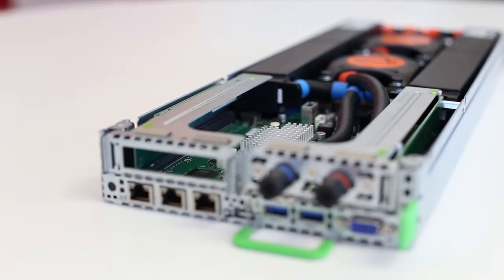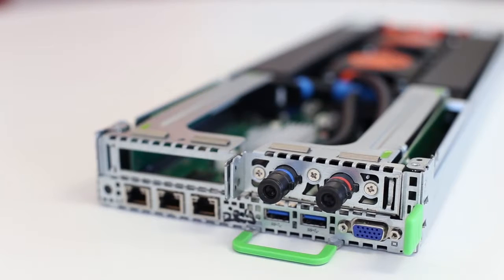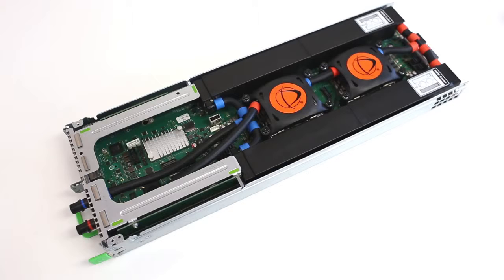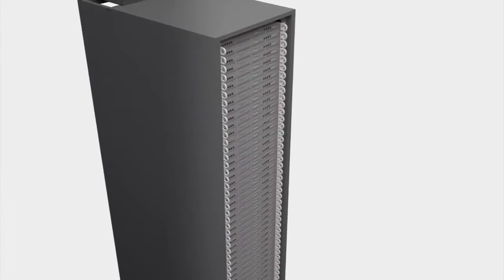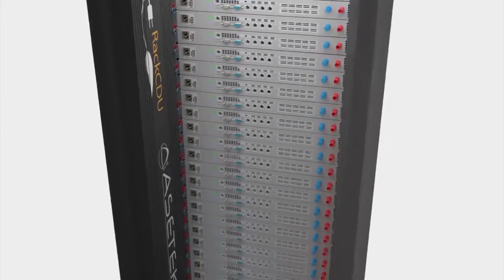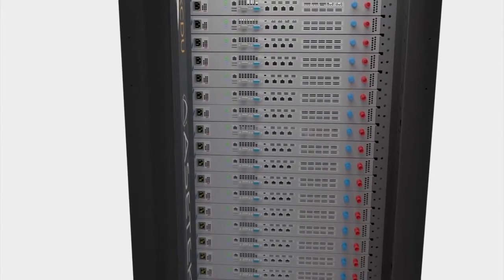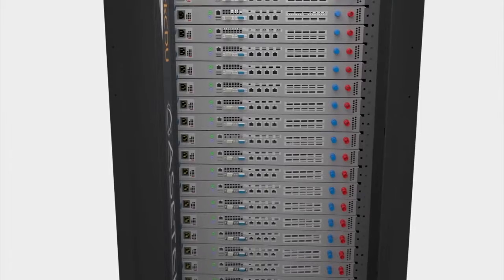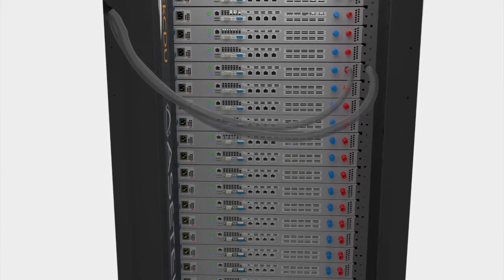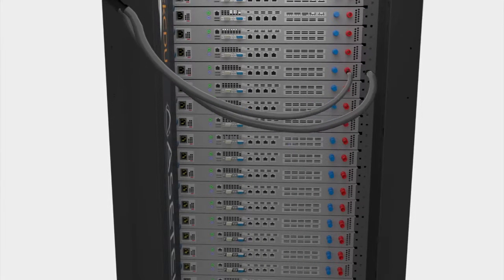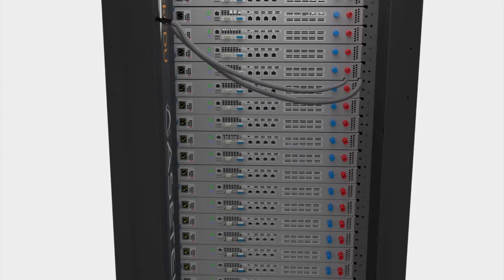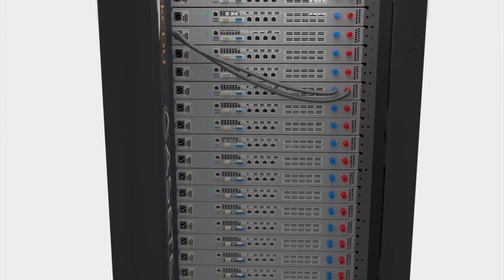Both PRIMERGY CX400 multi-node servers are now available in a special liquid cooling version. In these systems, 2 redundant pumps and cold plates on the CPU and memory modules capture between 70 and 80% of the server's heat. The liquid cooling sets in the servers are connected to a coolant distribution unit via tubes with quick connects. Very low liquid pressures on the server side and dripless double-sealed connectors guarantee highest protection against liquid spills.